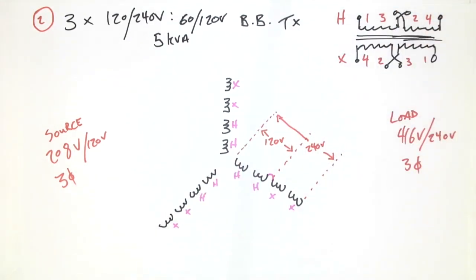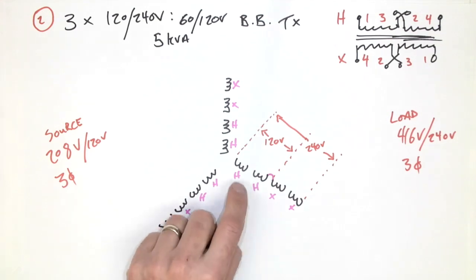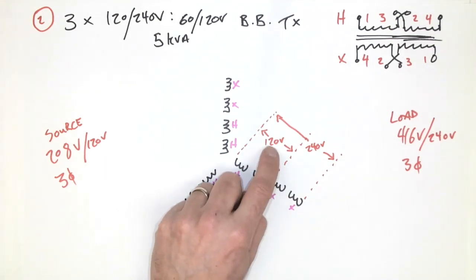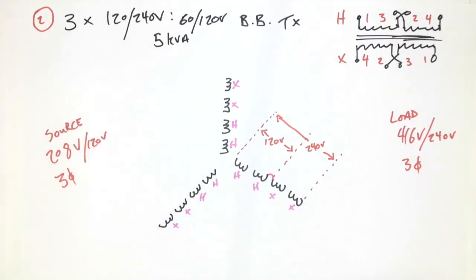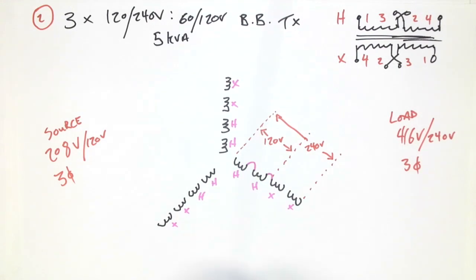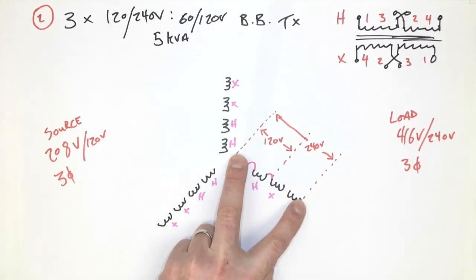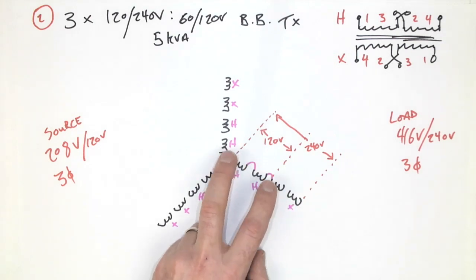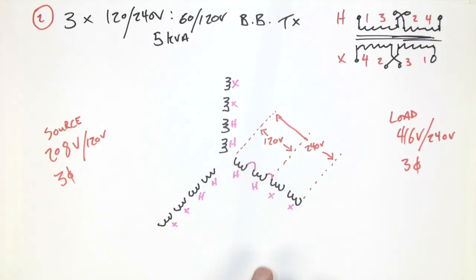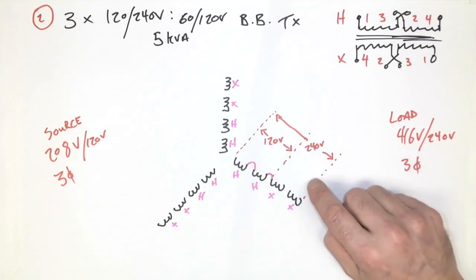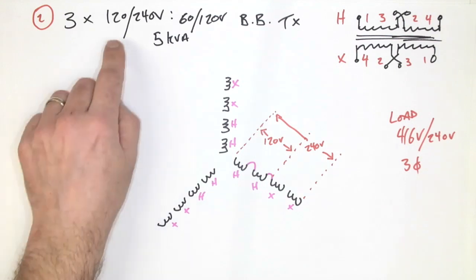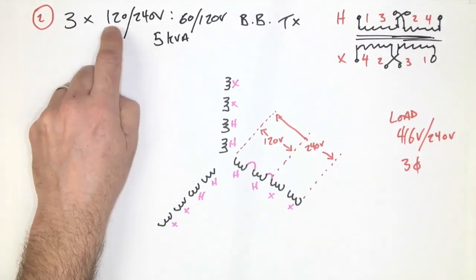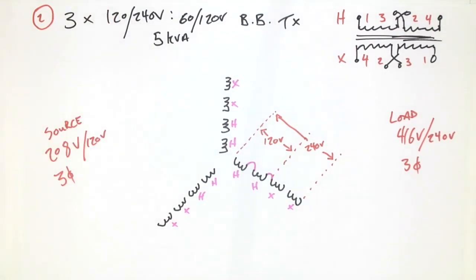Now that I have those 2 voltages, we can look at what is necessary for my winding connections in order to achieve this. On the H windings, in order to get 120, I would need to put them in series. So let's do a series connection. If I were to get 240 from here to here, that would mean, well, series 120, 240, right? And over here, 60 and 120. Let's take a look, 240 volts, 120 plus another 120. I've just done that wrong, haven't I? The 120 would be if it was in parallel. There we go, so let's correct that, shall we?